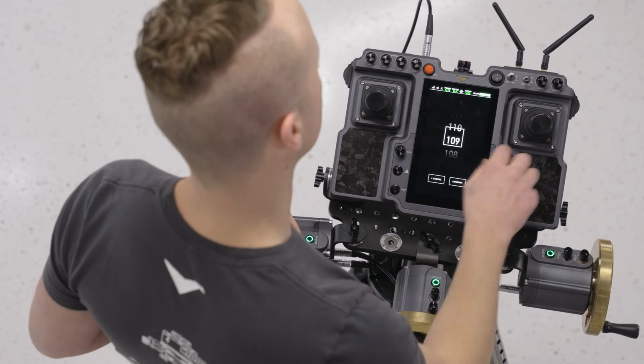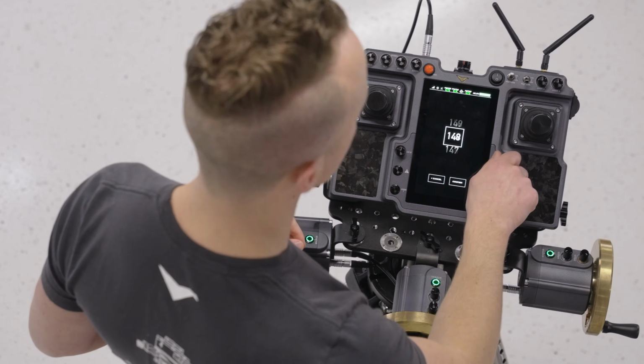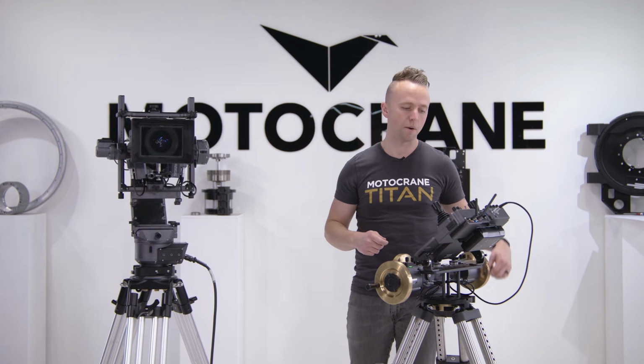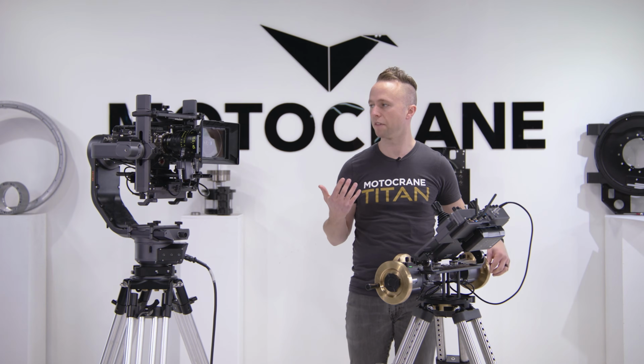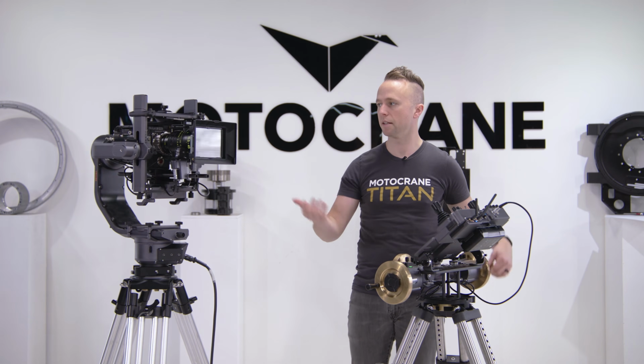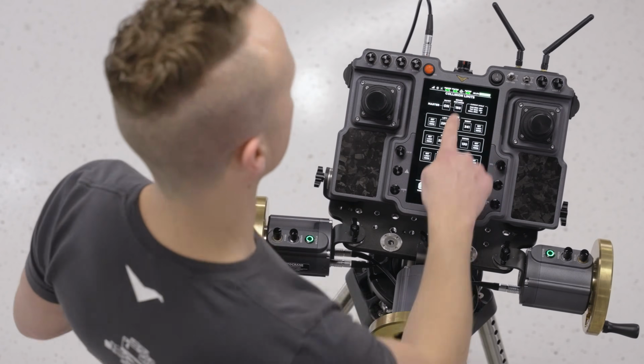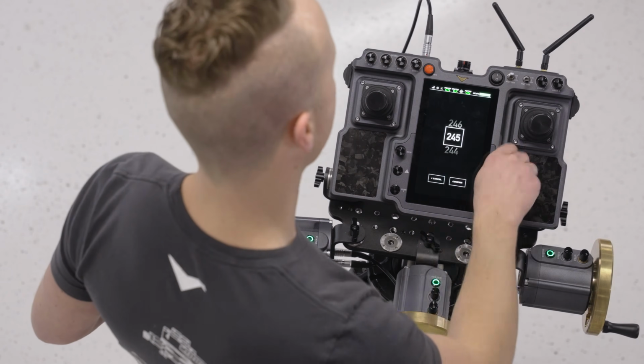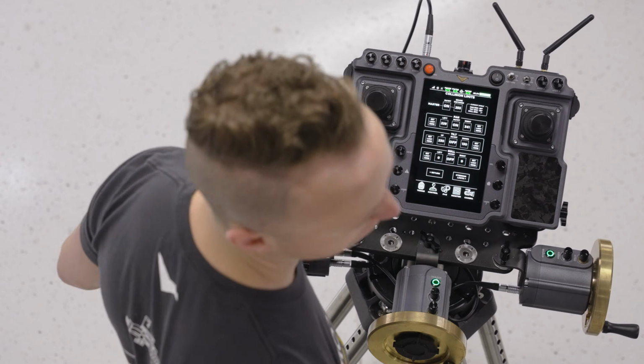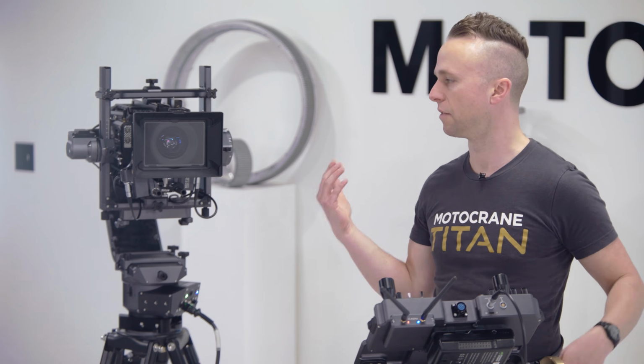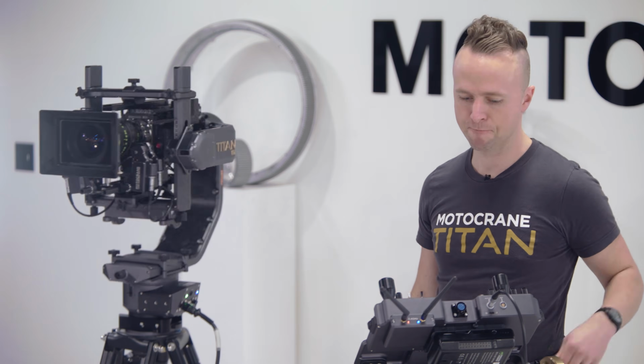The typical value is around 100. You can bring that up to 150 or so if you want it a little softer. Now as I approach the limit, there's a little softening that happens as I hit it. I can increase it all the way up to the maximum if I want it to be as soft as possible for an operator, and as I get there, we have a nice ease into that limit.